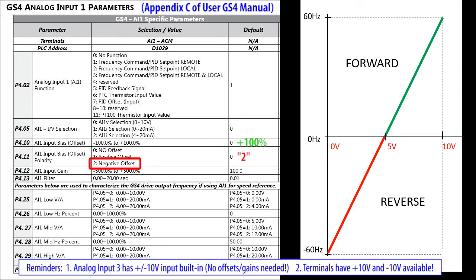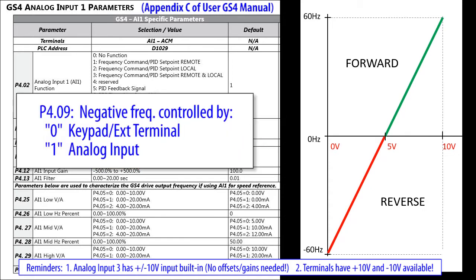That's so if you have a PLC that can only write positive values, you can invert them here. Finally, in parameter 409, we tell the drive to use the analog input for forward and reverse instead of the keypad or external terminal.